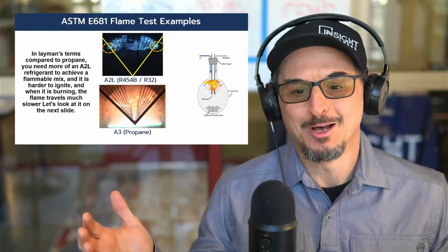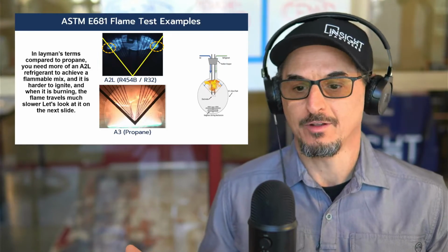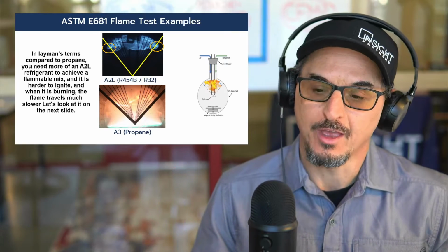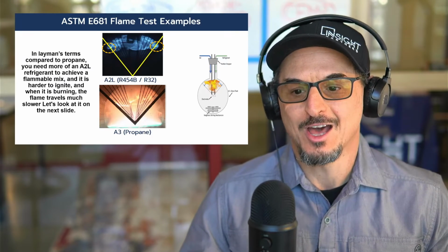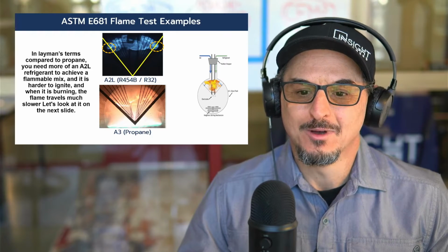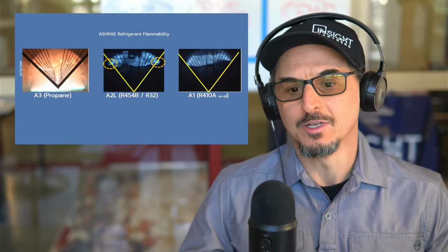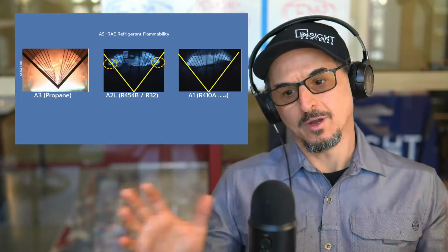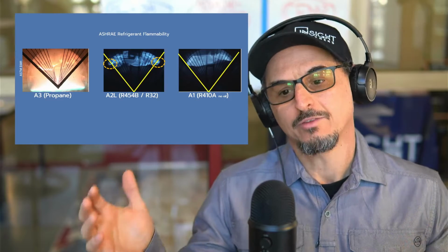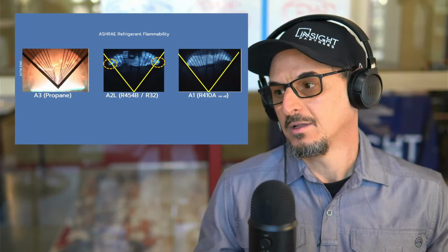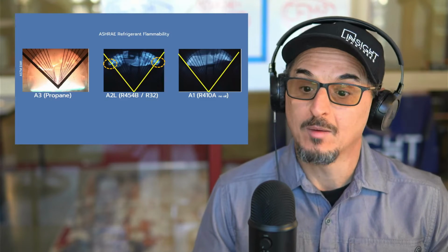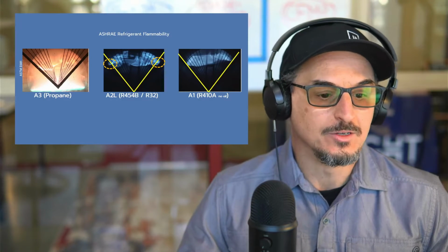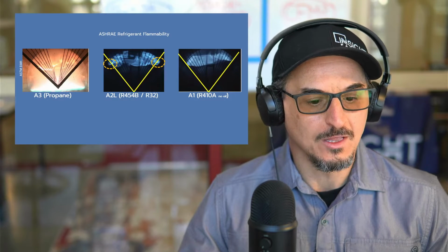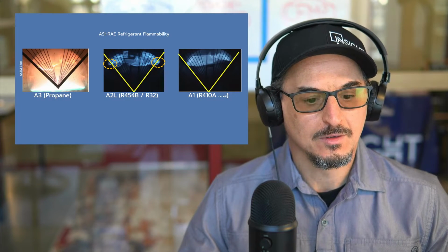In comparison of an A2L to an A3, you can see it's an enormous difference. When I think of flammable, I think of what this A3 propane picture is showing, which is not at all what we get with the A2L. So that's a good comparison. This chart kind of sums it up for me. You could Google flame tests on YouTube and see actual footage - it has to do with flame propagation, how fast it spreads, how much ignition energy is required to ignite the refrigerants, etc. There's a lot of things involved in the actual test.